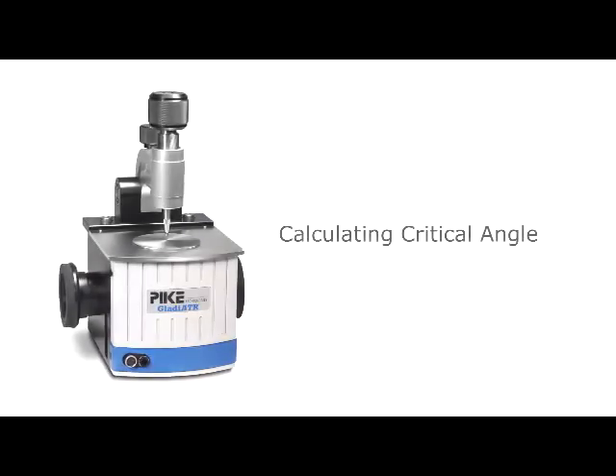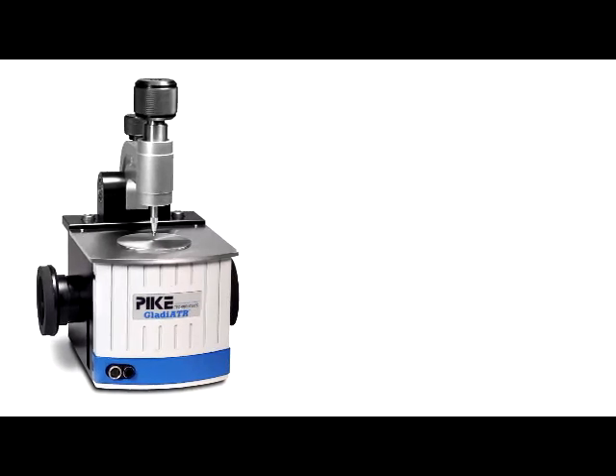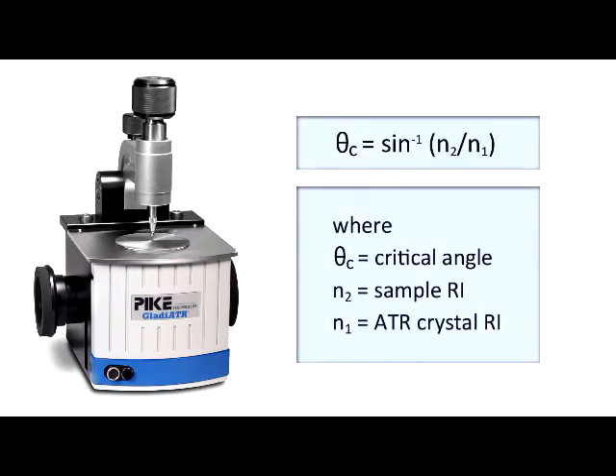ATR sampling requires that the accessory's angle of incidence is greater than the critical angle, which is defined as the inverse sine of the ratio of the sample and crystal refractive indices.